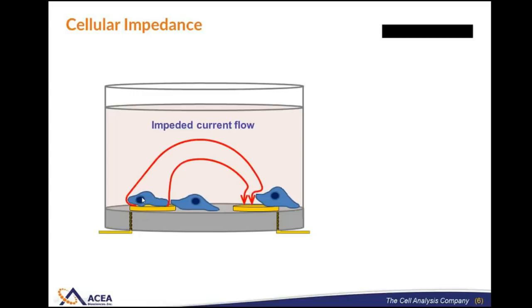This works with bacteria and a wide variety of cell types. As cells adhere to the electrodes in the well bottom, this is physically a much different situation. Cells are not naturally good conductors of electric current — they're insulators. There is now an inherent resistance in the system to the flow of current from one electrode to the next. xCELLigence monitors how hard it has to work to maintain a constant flow of current as cells grow, proliferate, and change shape on these electrode surfaces.